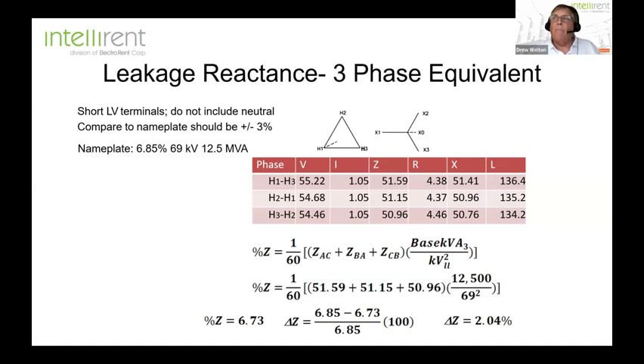Number one, if you have a through fault monitor and you've seen a number of occurrences between the testing intervals, then you'll want to run a leakage reactance test. It's your first indication that you may have physical damage. The other is, what if you don't have a monitor on there? You don't know if you've had through faults or not. Well, probably a good idea to incorporate a leakage reactance test.